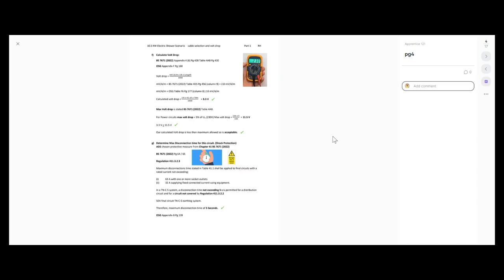There are still a couple of other considerations to make sure this circuit fully complies with the requirements of the regs. The next stage — which we didn't get this far last week — is to work out whether the circuit is going to disconnect under fault conditions: shock protection. I need to determine what the maximum disconnection time allowed is for this circuit. When we go into Chapter 41 of the regs, the most common protective measure is automatic disconnection of supply. Looking at regulation 411.3.2.3 on pages 64 and 65, it talks about maximum disconnection times, stated in Table 41.1, for final circuits with rated current not exceeding certain values.